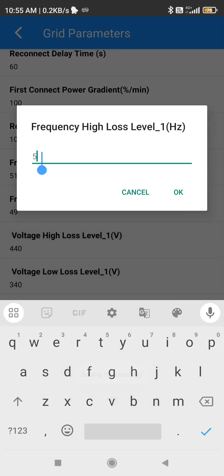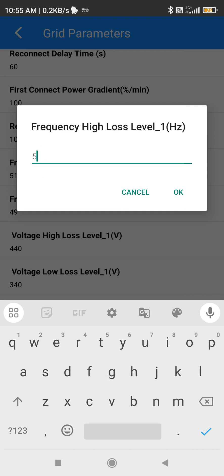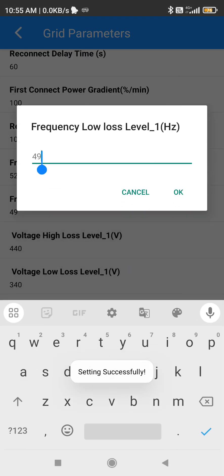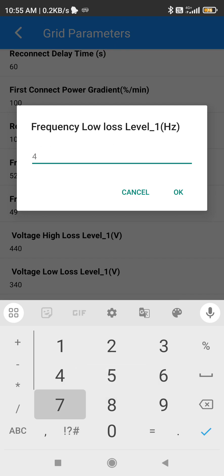For frequency, the High Frequency will be 51 by standard — you have to change it to 52. For Low Frequency, it will be 49 by default — you have to change it to 47.